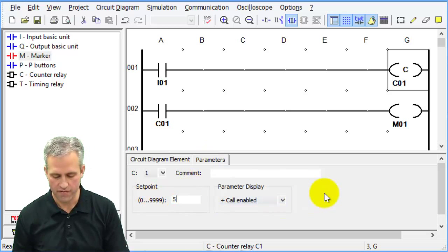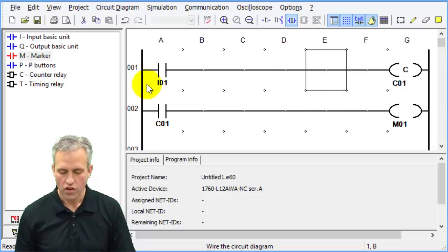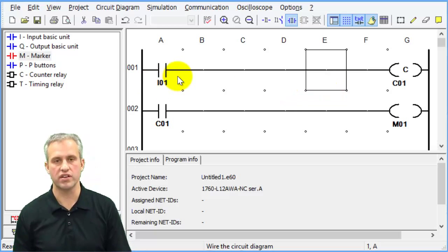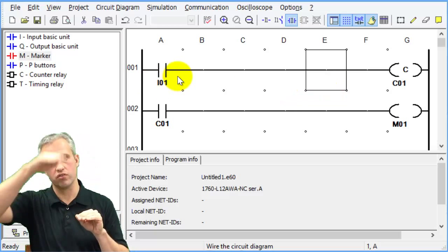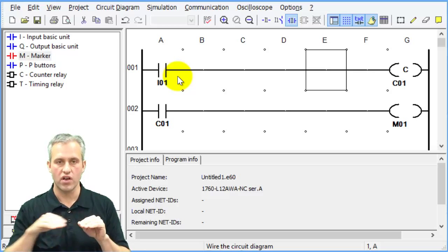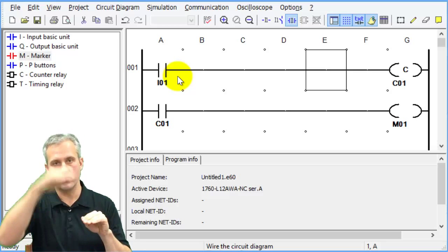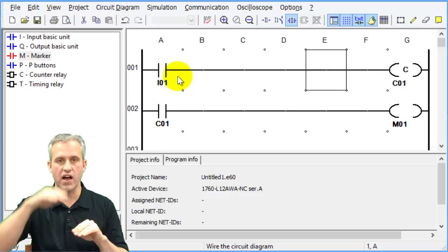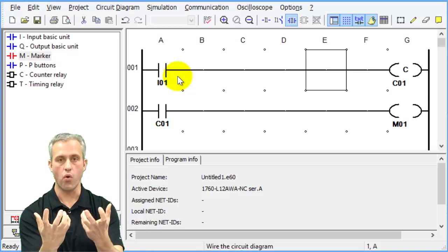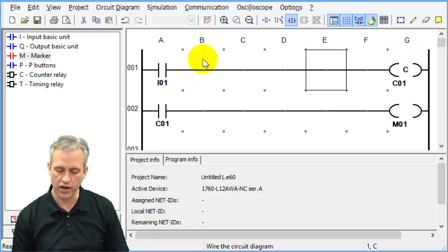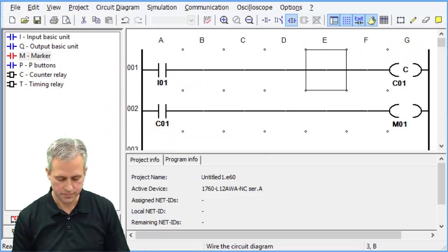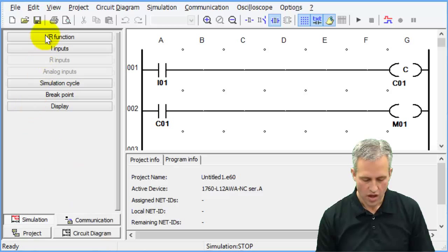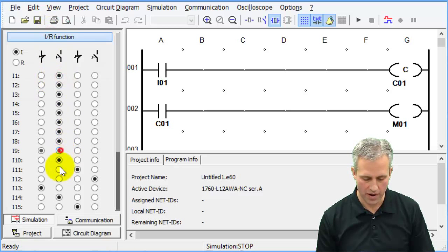So in this case, you're going to create a set point of five. So what it does is it counts pulses, it counts rising edges of I1 in this case. As soon as it sees five of them, then it comes on. And so once it's on, it's going to control marker one.